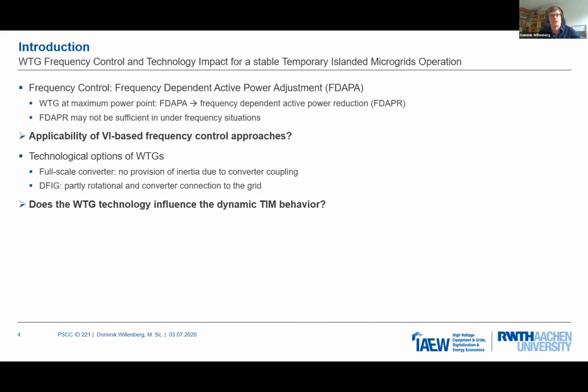So if we think about the frequency control approach, as mentioned before, WTG units usually operate in normal operation at their maximum power point. So this FDAPA control approach reduces to a frequency dependent active power reduction. But here the question arises that this reduction may not be sufficient, of course, in under frequency situations.